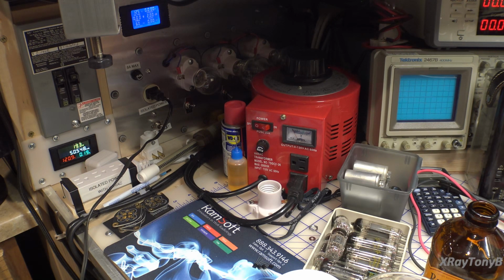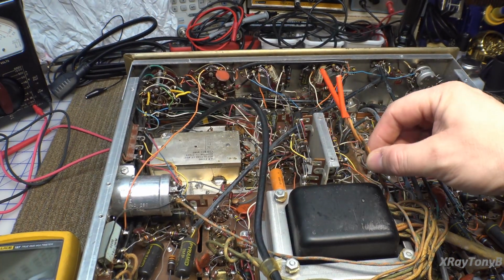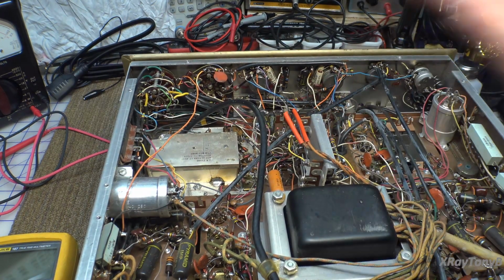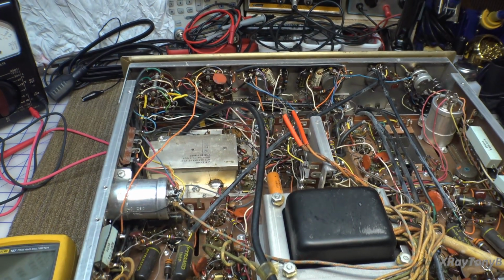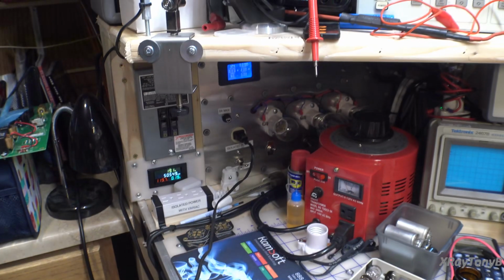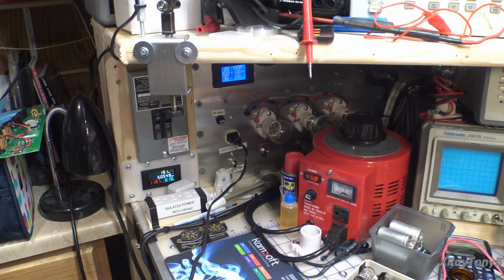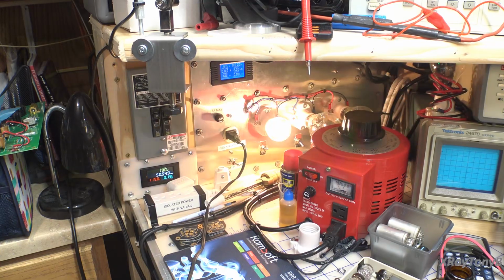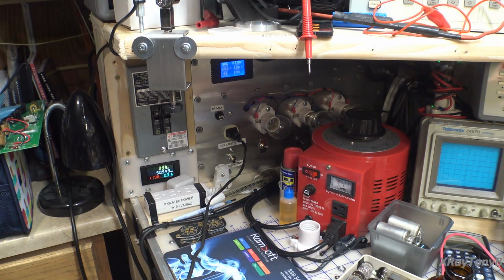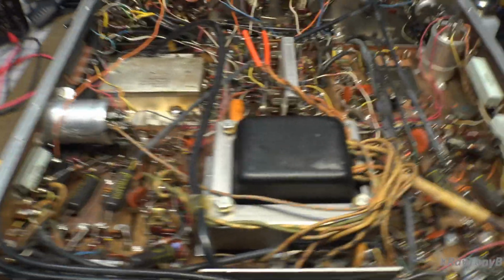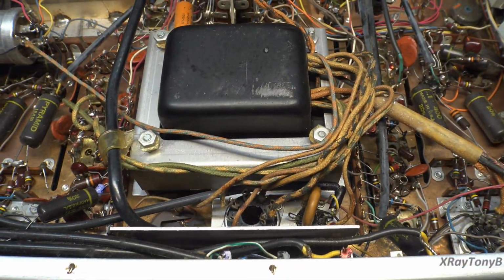Let's look at the solid state rectifier first. We'll disconnect that — if the problem doesn't go away, we're running out of options here. All right, I've now removed the windings from the solid state rectifier in case it's shorted. Let's turn this on. That is not a good sign, guys. It would be absolutely devastating if this transformer was bad.